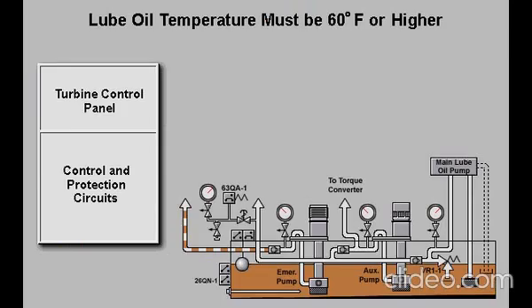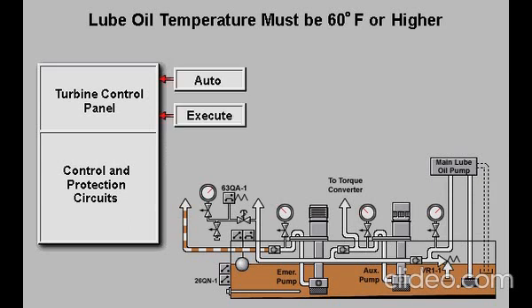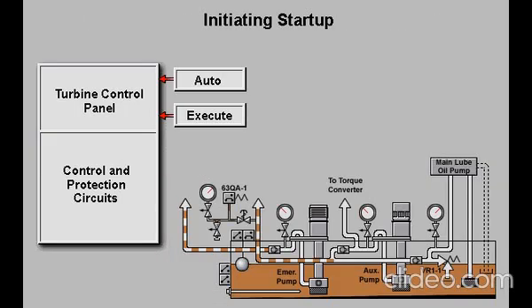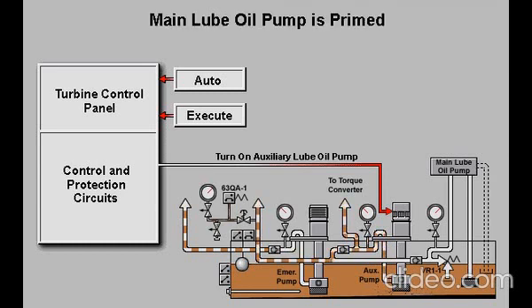During a normal turbine startup procedure, the lead operator will select Auto and execute on the operator interface of the turbine control panel. The protection system will check for a ready-to-start permissive from lube oil tank temperature switch 26QN-1. Turbine startup will not be permitted unless the oil temperature is 60 degrees Fahrenheit or higher. If all protection system checks are satisfactory, the auxiliary lube oil pump will start and the turbine will begin its crank cycle. The orifice check valve between the auxiliary pump discharge and the main pump discharge provides lube oil flow from the auxiliary pump to lubricate and prime the main pump at startup.